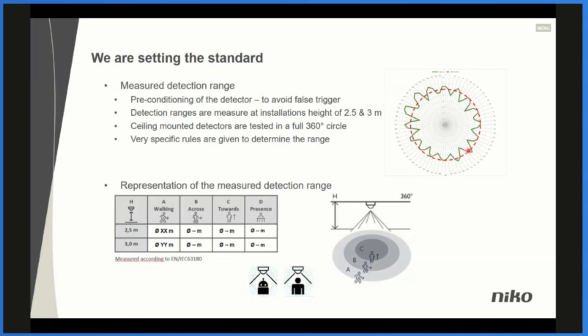And the representation of the measured detection in our product sheets will be as the following table, where you have the installation heights of 2.5 and 3 meters. Then you have the walking detection range, and by walking I mean you move through the detector. Then you have the B, it's across, so there you move inside the detection range. The C is the radial detection range, which is the most challenging parameter or detection range for any detector. And then the last one is the presence, where you are just right below the detector. And all the specifications for the detection range are according to 2.5 or 3 meters.